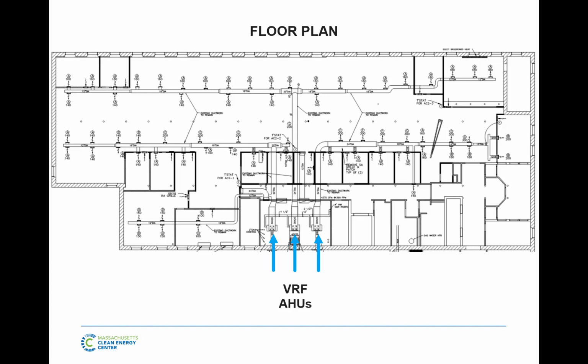So what that means is these days, one of the big developments is if the regular fan coils that Greg talked about don't work, you can build semi-custom VRF air handlers. So here that was the idea. You still get the advantage of the VRF heating and cooling, energy efficiency, comfort, and all that. We just didn't go in and put fan coils everywhere because they didn't want to zone it. They wanted to keep it the same way.